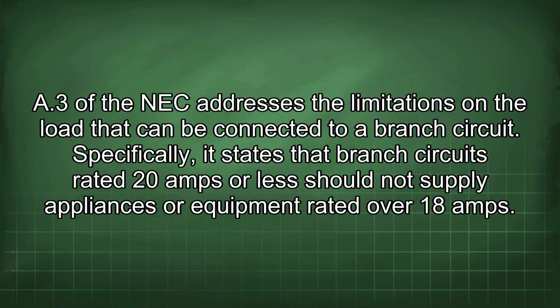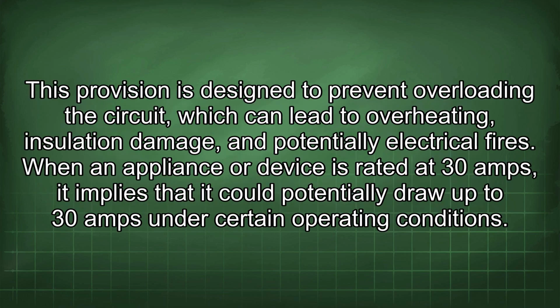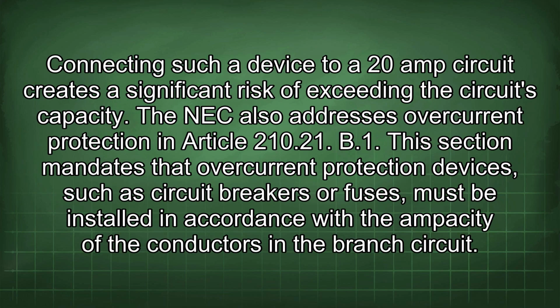Specifically, it states that branch circuits rated 20 amps or less should not supply appliances or equipment rated over 18 amps. This provision is designed to prevent overloading the circuit, which can lead to overheating, insulation damage, and potentially electrical fires. When an appliance or device is rated at 30 amps, it implies that it could potentially draw up to 30 amps under certain operating conditions. Connecting such a device to a 20 amp circuit creates a significant risk of exceeding the circuit's capacity.